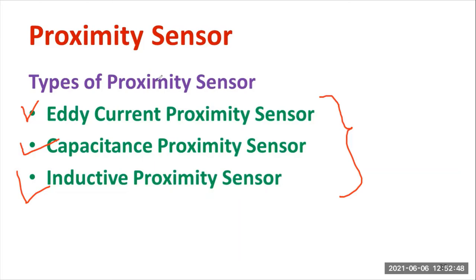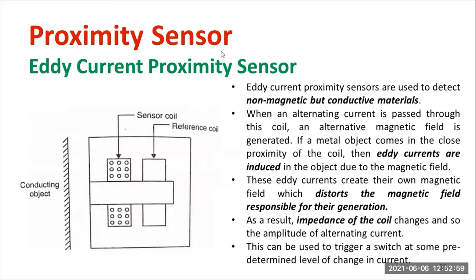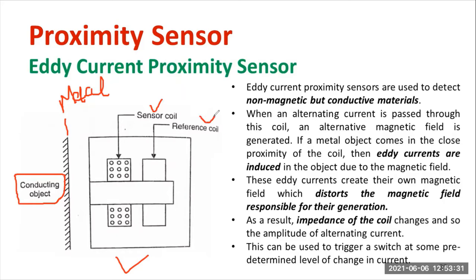Now let's understand how the eddy current type proximity sensor operates. Looking at the diagram, this is the object whose presence needs to be identified — it is a metal object. On the right side, you can see the proximity sensor part, which has both a sensor coil and a reference coil. Imagine this as a 2D diagram in a 3D manner. You need to pass an alternating current through both the reference and sensor coils.